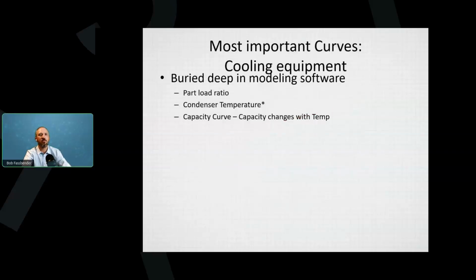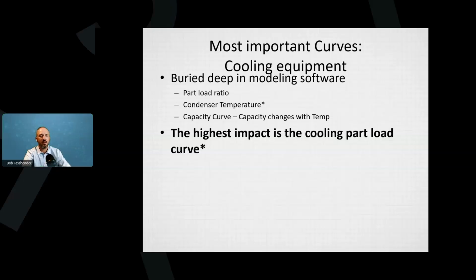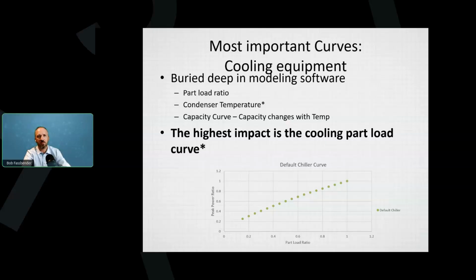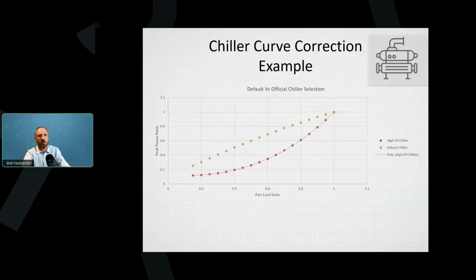Okay, so the most important curve, and you don't necessarily have to decide on this curve, but it's good to know. Sometimes I plot it out, because the highest impact curve that you'll have in the model is the cooling part load curve. Here's a default, and I'm going to show you what this one ran. This was someone's default; they were estimating their savings for a high efficiency chiller. I looked at the actual curve. The shaded area is the amount of time it's spent within the curve. And anyway, the two multipliers here, if you take the time to go through this, which we won't, it ended up using 50% of the energy that the model said it would initially.